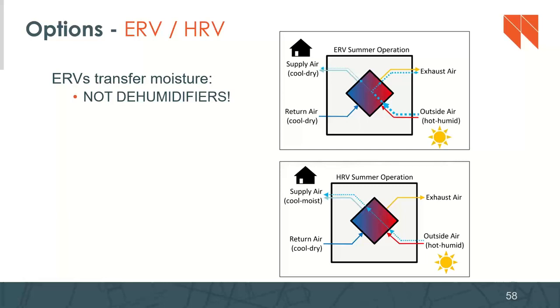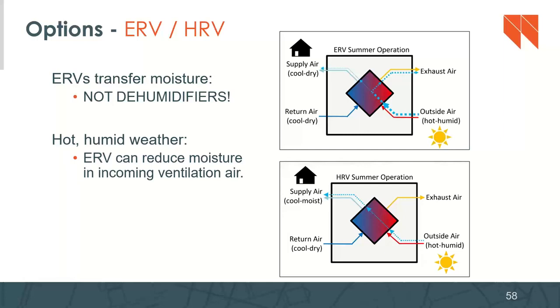I hear this quite a bit, even within the industry, that an ERV is a dehumidifier. It's not. What an ERV is going to do, it can reduce moisture of incoming ventilation air, but it all depends on which air is more humid, right? So during summer operation, you've got hot, humid outside air, and the return air is cool and dry.